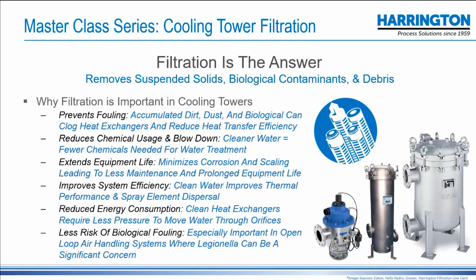So filtration is obviously the answer. It removes the suspended solids. It'll deal with biological contaminants and debris. And if you have the right technology, you will even reduce the scale-causing constituents, thereby reducing the chemical cost for anti-corrosives and scalants. So filtration will prevent fouling. It reduces your chemical usage significantly, and the blowdown.